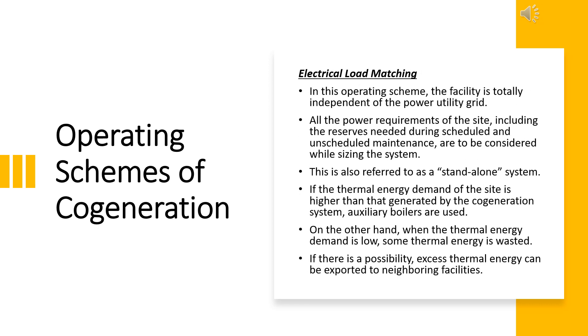The third scheme is electrical load matching. Unlike base electrical and base thermal load matching, in this operating scheme the system is totally independent of the power utility grid. All the power requirements of the site, including reserves needed during scheduled and unscheduled maintenance, are to be considered while sizing the system.